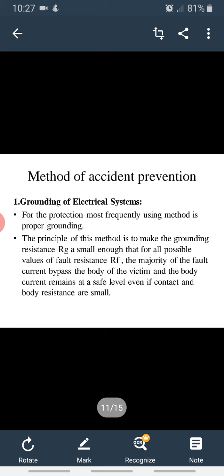Method of accident prevention. There are different methods. First one is grounding of electrical system. For the protection, the most frequently used method is proper grounding. The principle of this method is to make the grounding resistance Rg small enough for all possible values of fault resistance Rf. The majority of the fault current bypasses the body of the victim and the body current remains at a safe level even if the contact and body resistance are small.